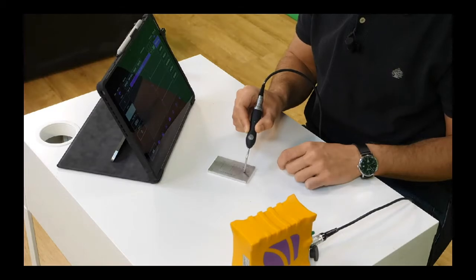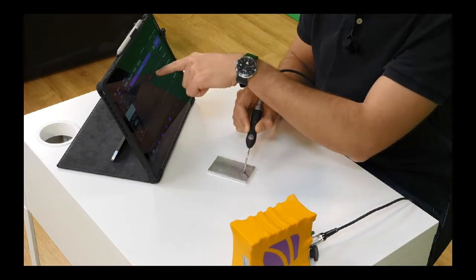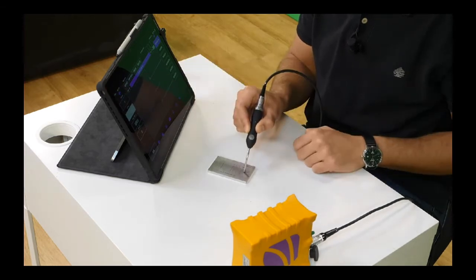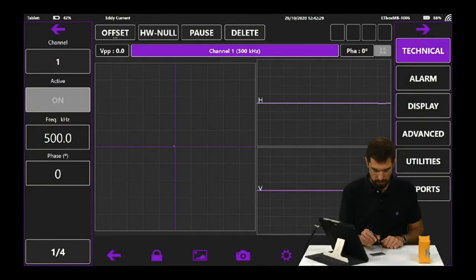As we can see, it's running now. Our signal is focused both in the horizontal and vertical components. To perform our calibration, we acquire the liftoff and the 3 notches.